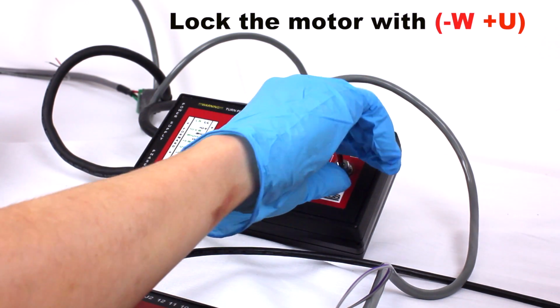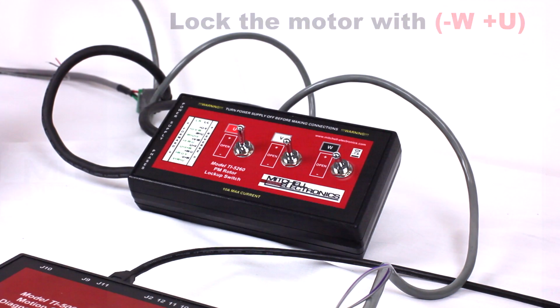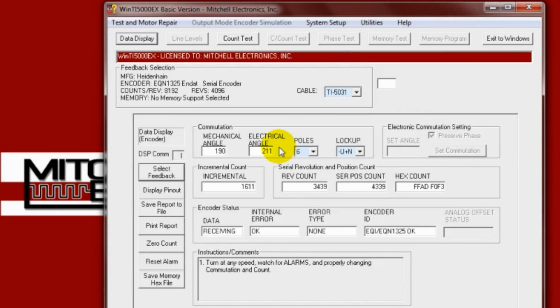Now lock the motor with minus W, plus U, and record the electrical angle. For Siemens motors, this angle should be 210 electrical degrees. This encoder tests well with no internal errors or counting issues. It is also aligned correctly to match the Siemens factory setting.